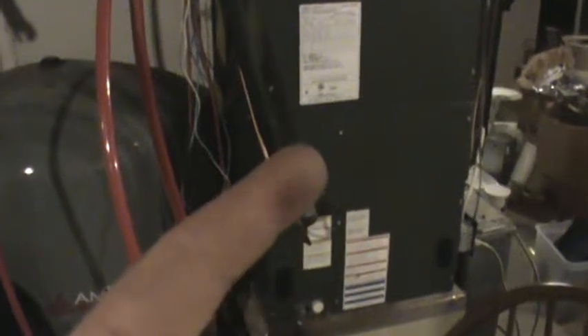Well, what happens if by some mistake the heat pump is running? Well, then you got really hot air going through here, and heat will actually not flow this way, it'll flow the other way and mess up the heat pump. So anyway, I don't like that. I wish that my heat exchanger for water to air from the boiler were up at the top, but I just didn't have a way to do that.